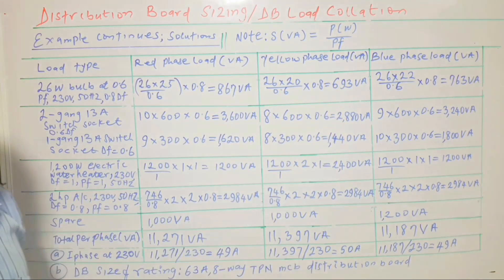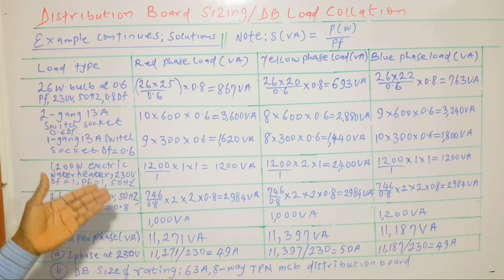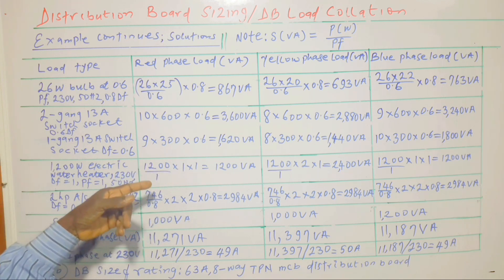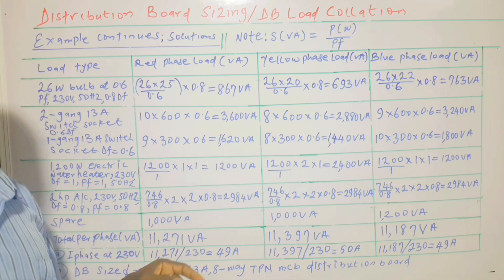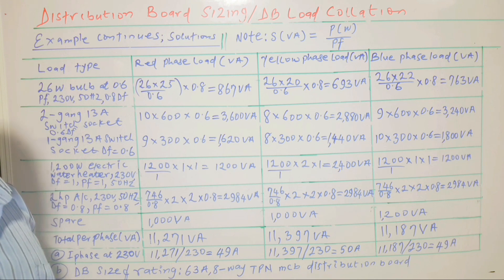Now we come to the electric water heater, which is a heating load. The power factor is 1, that's why the water heater power is being divided by 1. Then we multiply by 1 because only one is connected to the red phase, and the diversity factor is 1 since there are not many of them. We don't apply diversity factor when we don't have many of the items. Similar calculations hold for other phases.